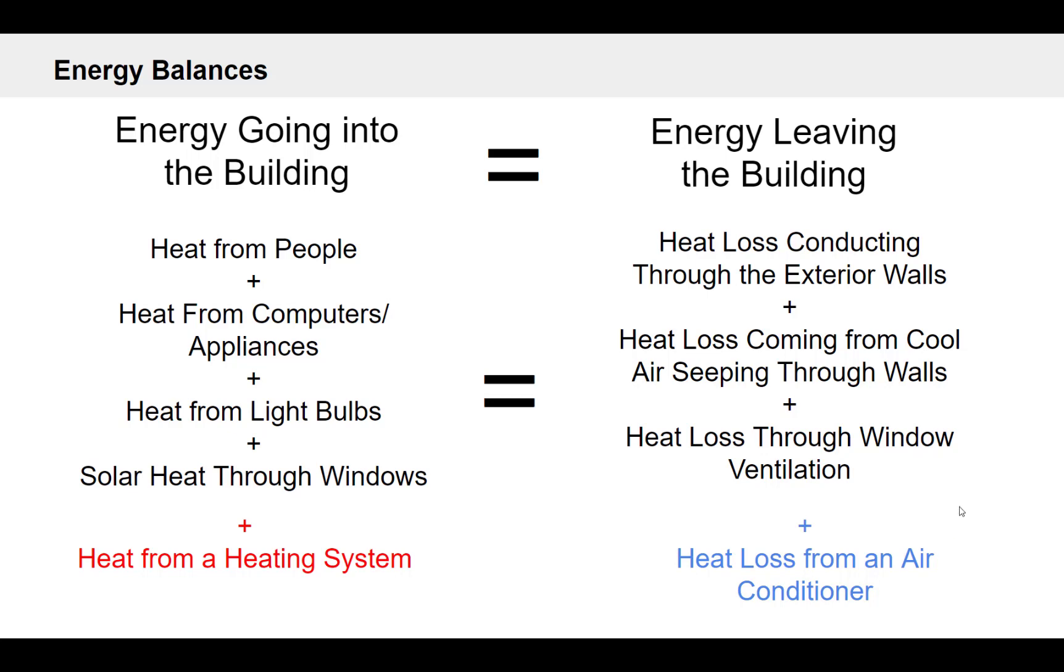And importantly, if these two things are not balanced, then our building is not going to be at a stable temperature. It's either going to be getting warmer if there's too much on this side and not enough on this side, or it's going to be getting colder if there's too much energy leaving the building and not enough going into it. And so the way that we're actually calculating the amount of heating or cooling that we need for this single-family home in our energy model is that those heating and cooling terms are just the remainder of whatever happens at the end of this calculation. In a very basic sense, all energy calculation engines are just running this same equality calculation that is the first law of thermodynamics over and over again for at least every hour of the year.